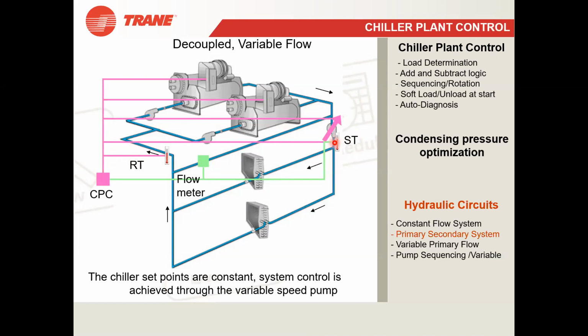If load is reduced, then we have to reduce the secondary pump speed. And the beauty of the secondary pump is that if you reduce the speed by 20%, then the energy saving will be 50%. So how? I will make it simpler. Suppose your occupancy level at the office has decreased. Now you do not need so much chilled water. So what will be done now? Primary will always throw you 100%, but secondary is now throwing to the AHU 50%.